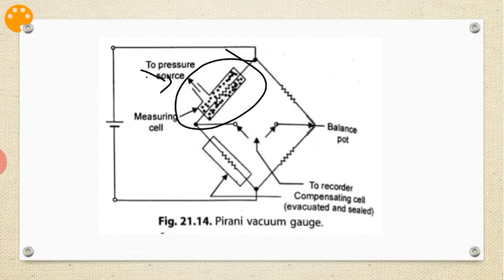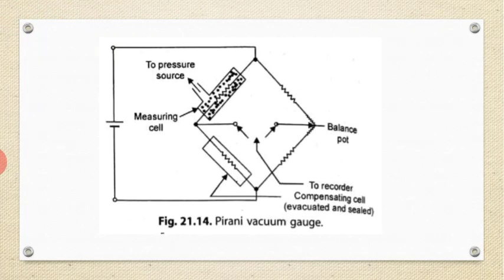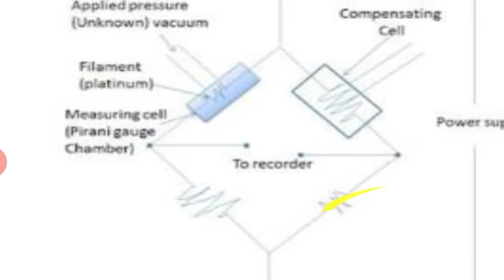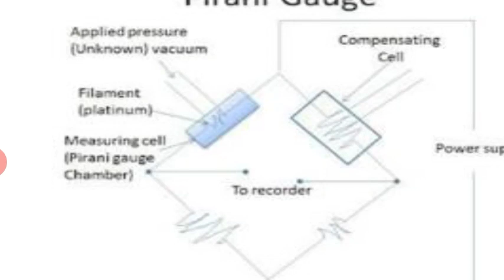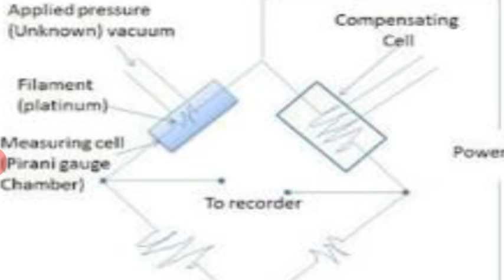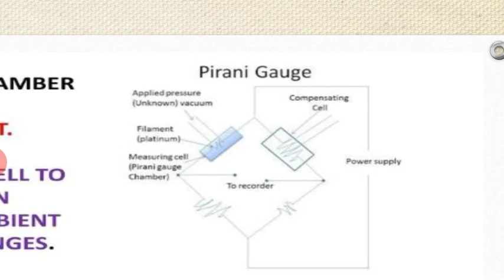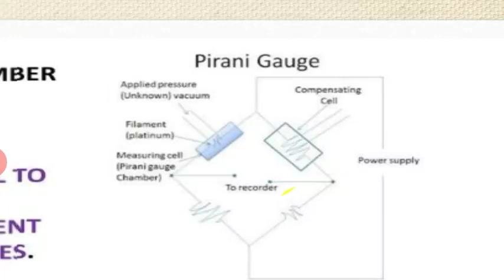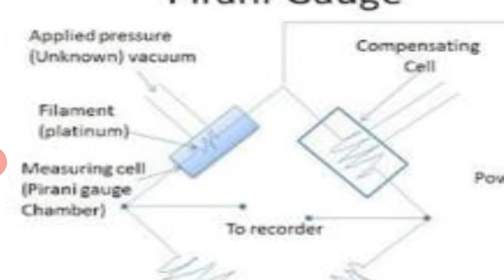Further, the Pirani gauge chamber and the compensating cell are housed in a Wheatstone bridge circuit, as shown in the diagram. Here you can see the compensating cell, which is introduced for compensating purposes. If any variation is there due to the ambient temperature, it will be compensated with the help of this.